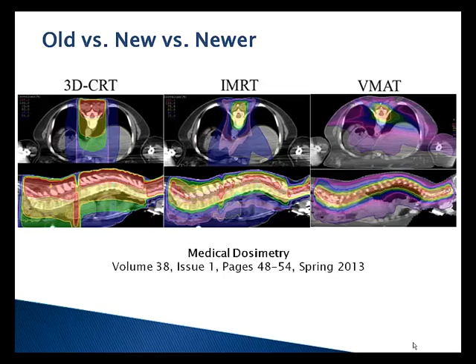My company makes QA equipment, and one of the first things I recognize is that when I use Pinnacle in my clinic, there's one planning system to QA. Now that I'm a QA vendor and we see the complexity that exists everywhere, it's a lot harder. There are different Linac coordinate systems. When your gantry is pointing down, that can mean 0 degrees, it can mean 180 degrees. I'm fairly amazed that this is allowed to change. Same with the centigray per MU. That is just completely determined by how your physicists would like to set up their centigray per MU for that linear accelerator. That's how we can get 30 or 40% calibration errors, because they're allowed to vary that much. MLC transmissions and capabilities vary greatly. There are tons of types of deliveries: static, moving gantry, MLC, small, large MLC segments, et cetera, et cetera.